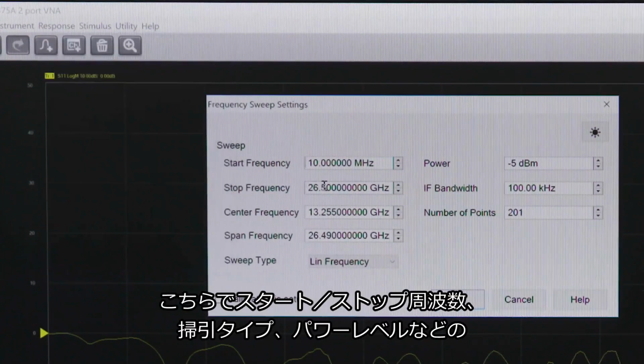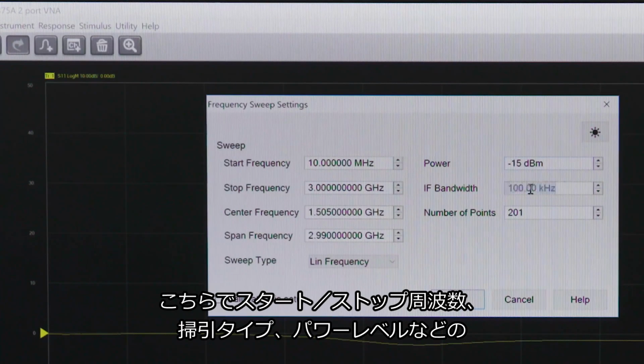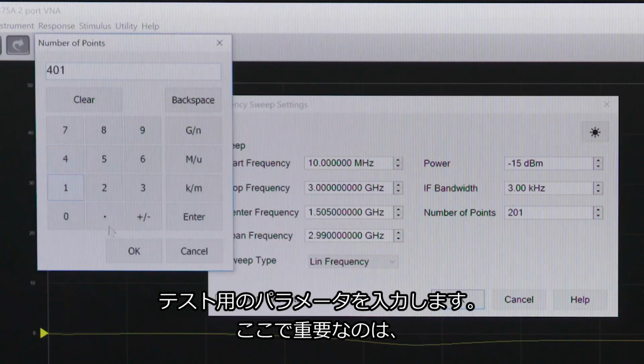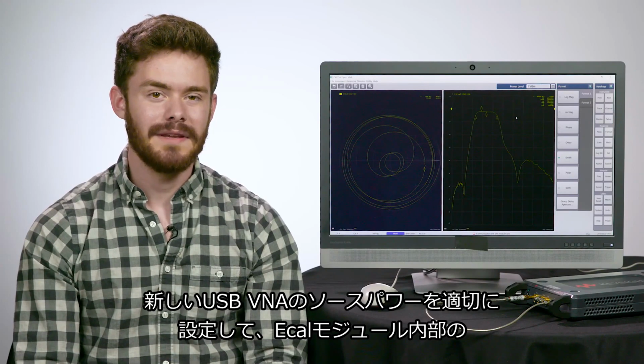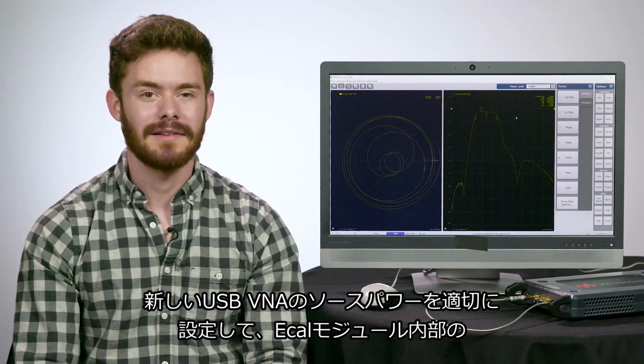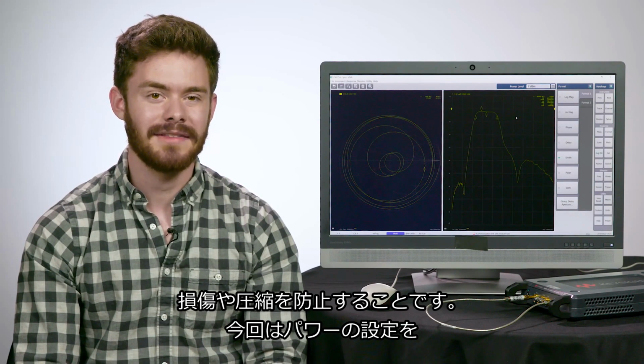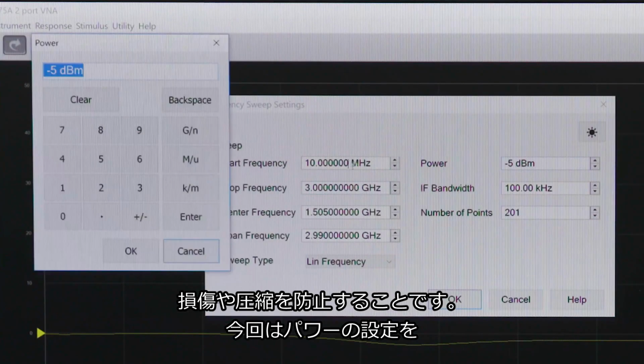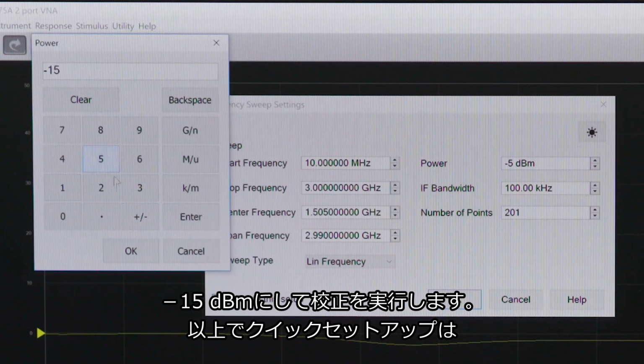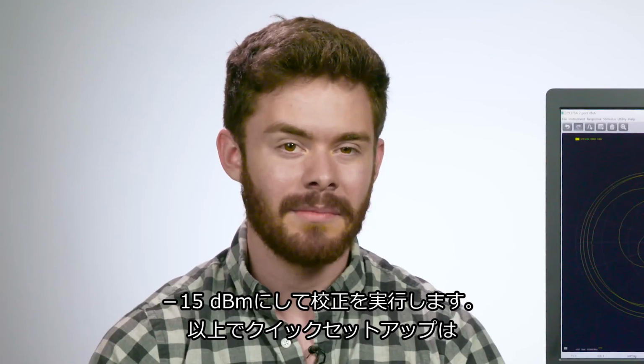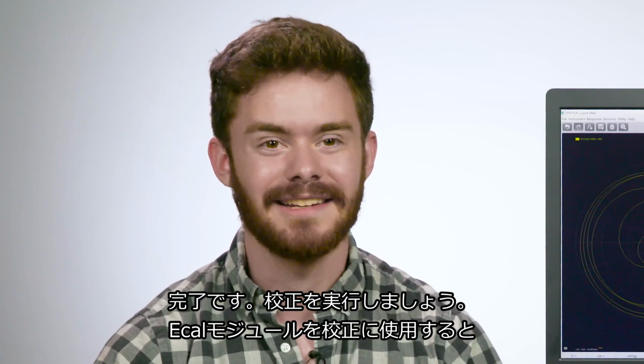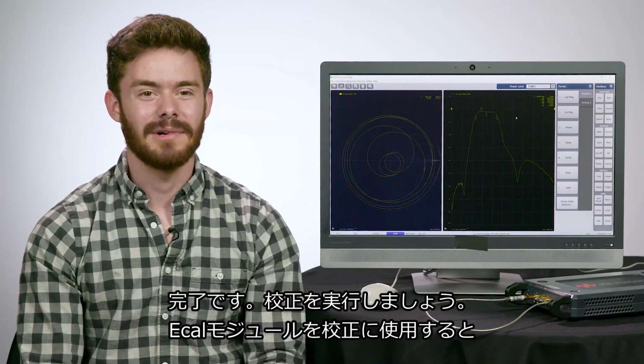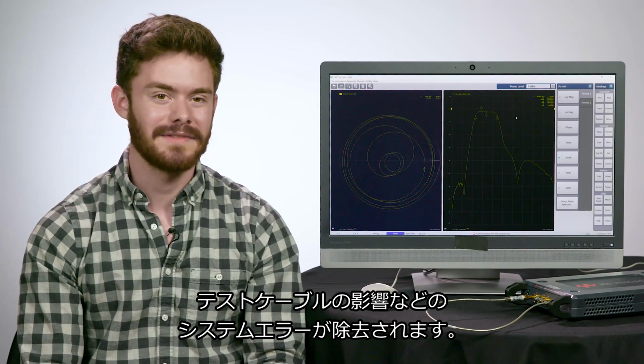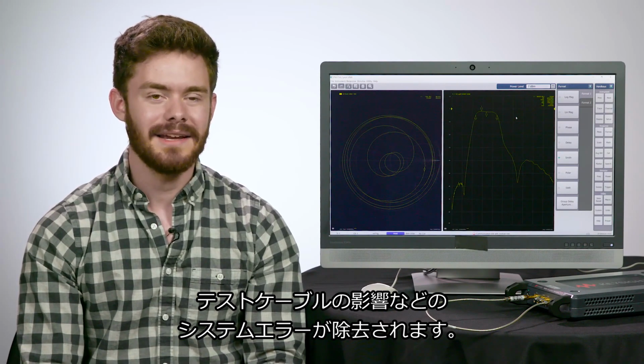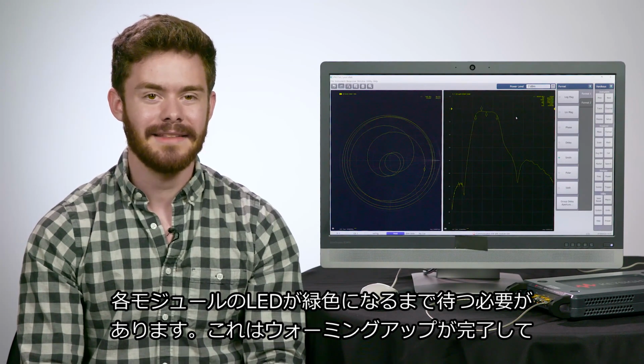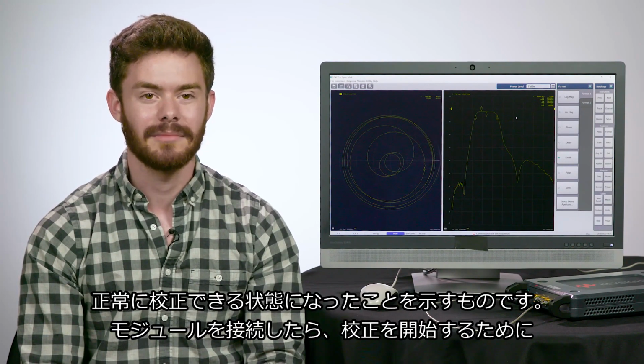This is where you will need to enter your start and stop frequencies, sweep type, power level, and the other parameters for your test. It's important to remember here that this new USB VNA's source power must be set correctly in order to avoid damage or compression inside the eCal module. The power for this should be set to -15 dBm for the calibration operation. Now that we're done with that quick setup, let's get calibrating. The eCal module is used for this calibration to remove system errors, like the effect of test cables. Wait until the LED of the eCal module turns green, indicating that it has warmed up enough in order to correctly calibrate.